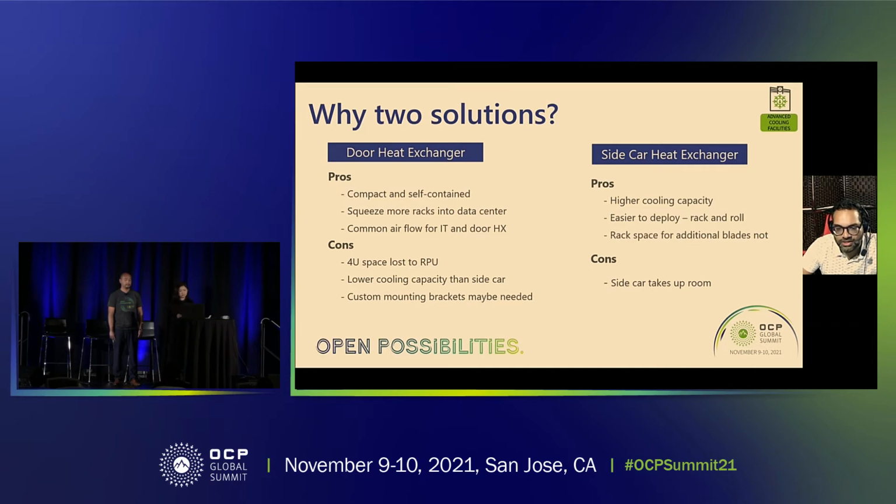The biggest con is definitely how much space the sidecar takes up. That additional room could be used by another IT rack, so that could be a significant con depending on the data center operator and economics.